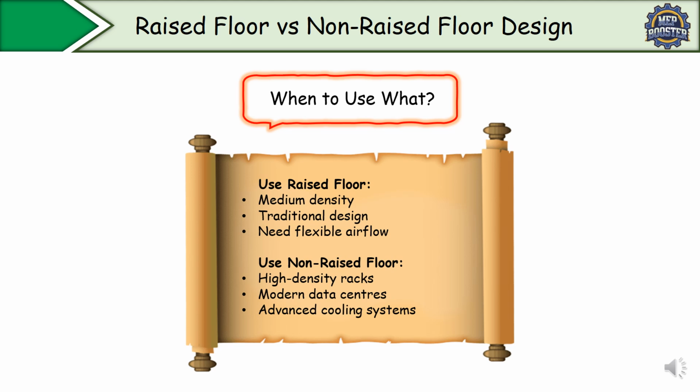Then for advanced cooling systems, it means you can use modern cooling technology: in-row cooling, rear door heat exchanger, liquid cooling. So why is the raised floor not needed here? Because cooling is localized and targeted here, so no need for underfloor air distribution. Okay. So in short, you can say the raised floor is used for flexible, traditional or medium load, and non-raised floor is used for modern, high load or advanced cooling. Got it? So this is all about the difference between raised floor and non-raised floor design.